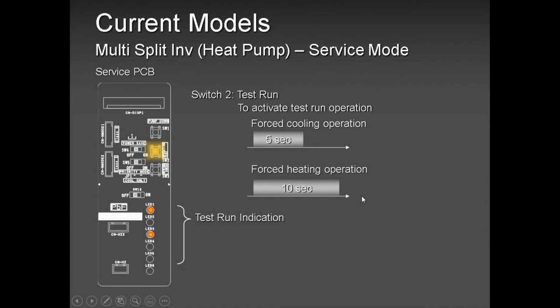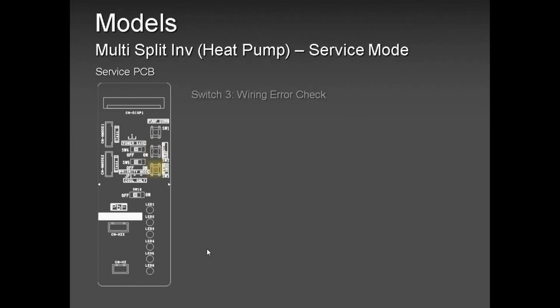Test run. Test run is a good feature to use when you have a problem. Let's say you have a leak, or you have a low refrigerant charge, or something is not right that the homeowner is complaining about. Test run is a good option to run the system because the compressor runs at a higher, fixed frequency, enough time for you to put your gauges on and see where the problem is. If you're low on gas, if you have a problem with the compressor, if you have a problem with the fan motor, or if you have a problem with the indoor unit, or you name it.